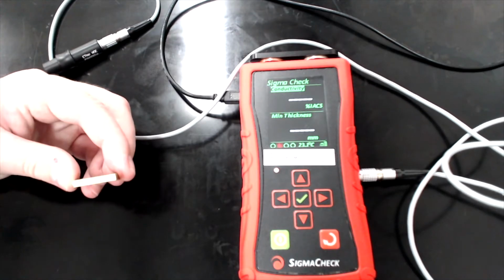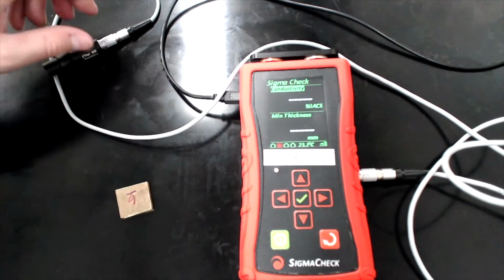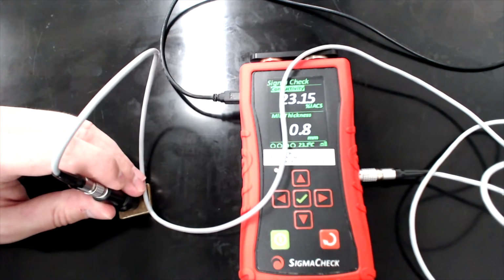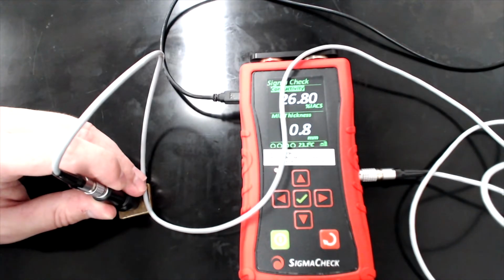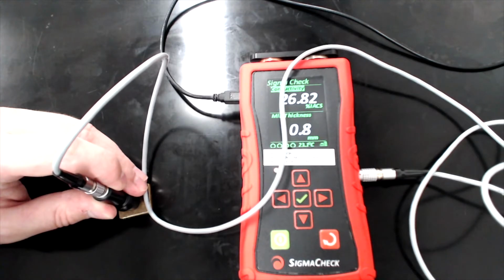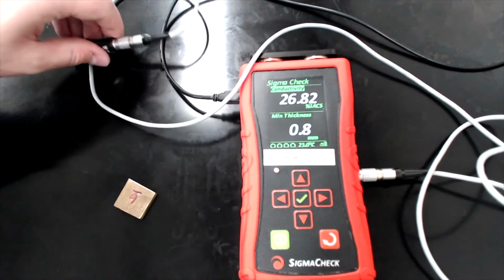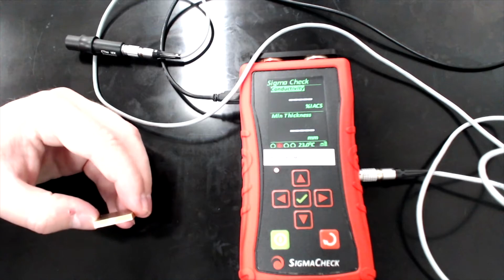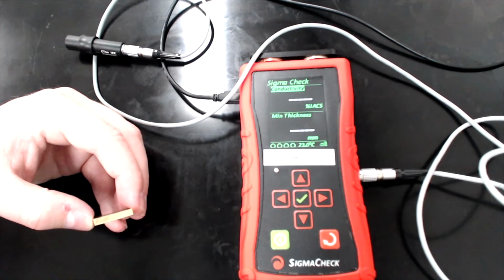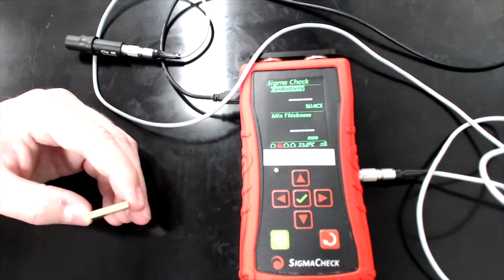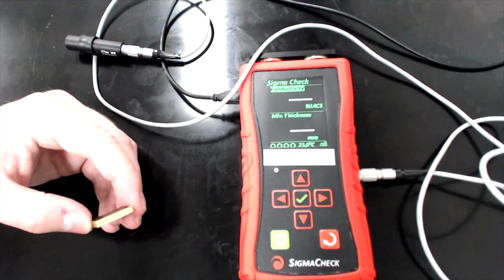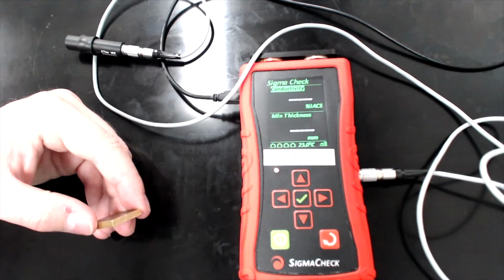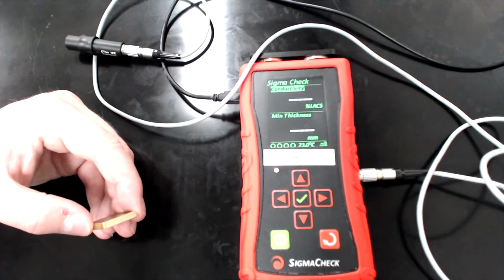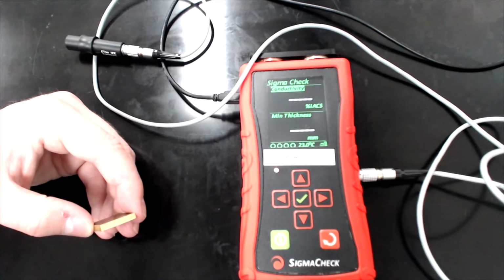So you'll notice that this sample is a given thickness. If I press the probe here, you're going to see that the minimum thickness should be 0.8 millimeters based on the conductivity and based on the probe settings that we have. So if I measure the thickness of this and it's not at least 0.8 millimeters thick, then that wouldn't be a valid test. And so we would want to go back and change, most likely, the probe frequency such that that minimum thickness decreases. And we'll go over how to do that.